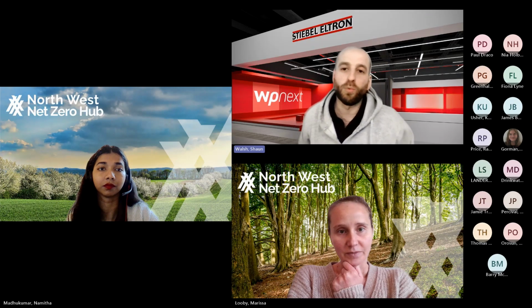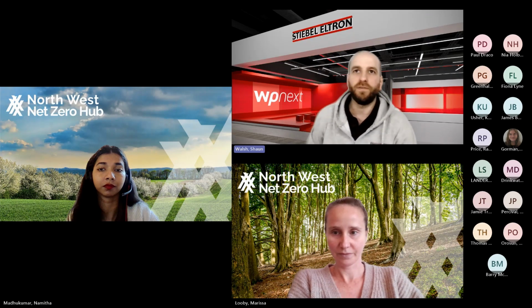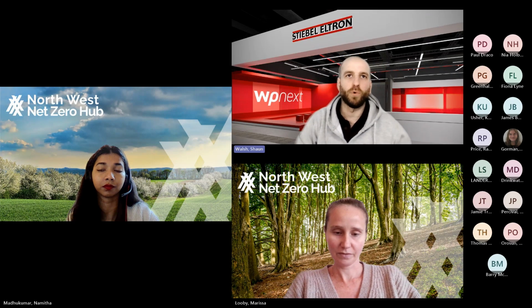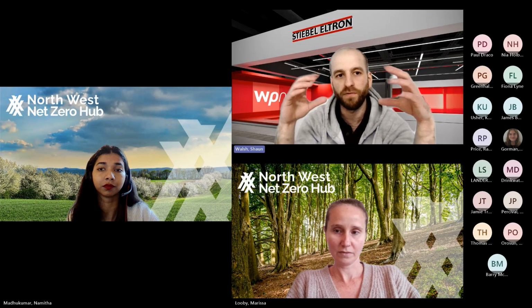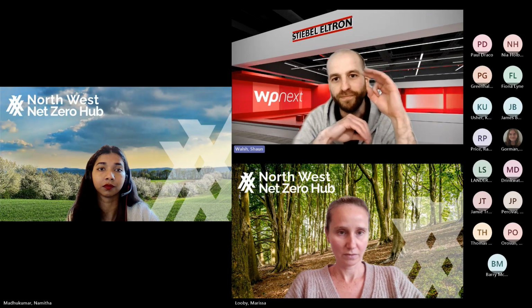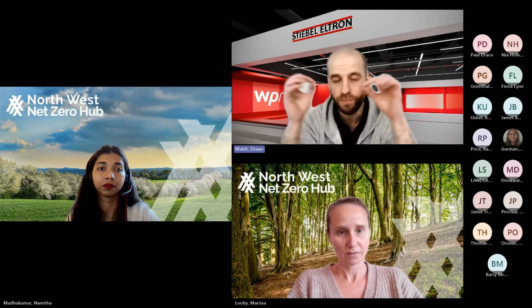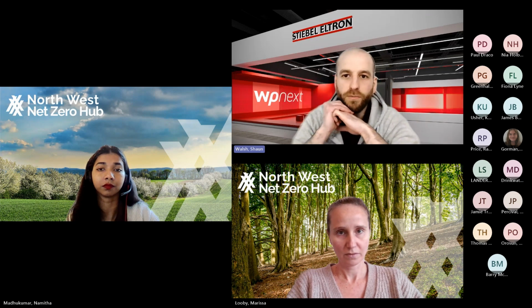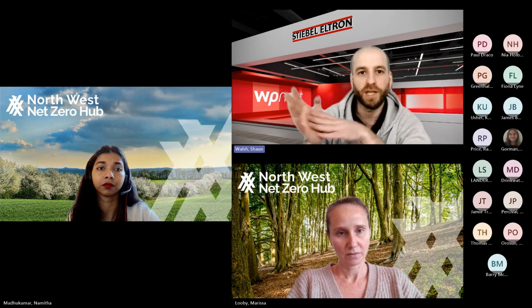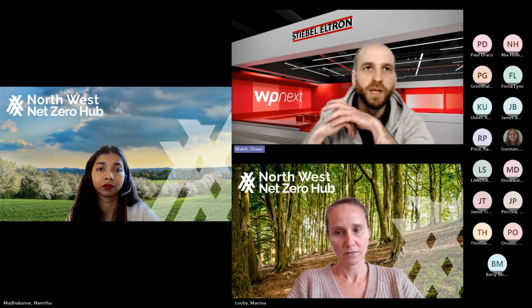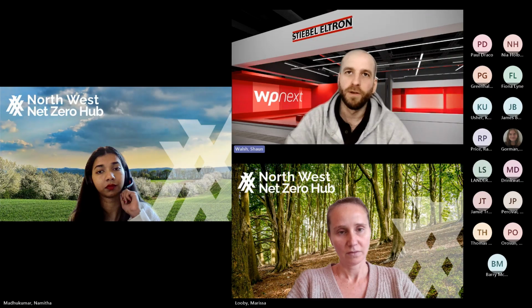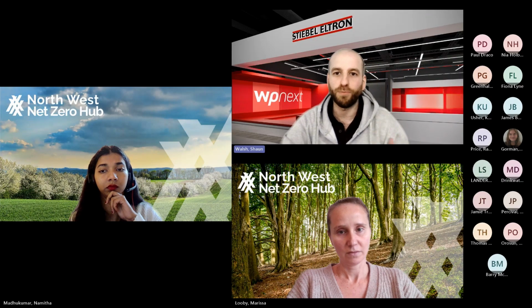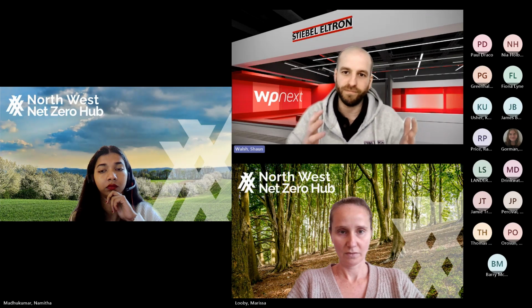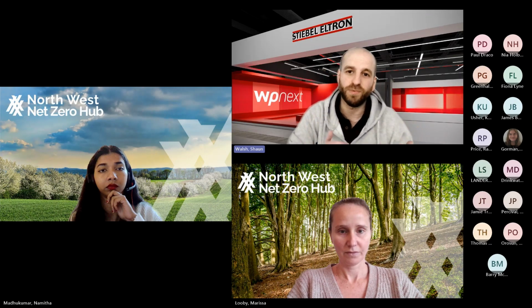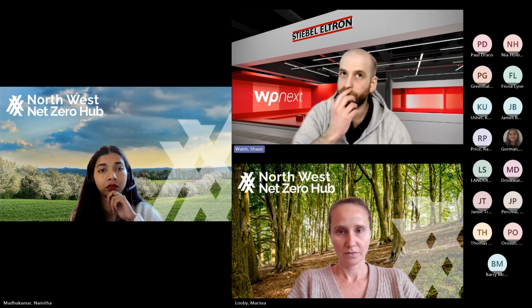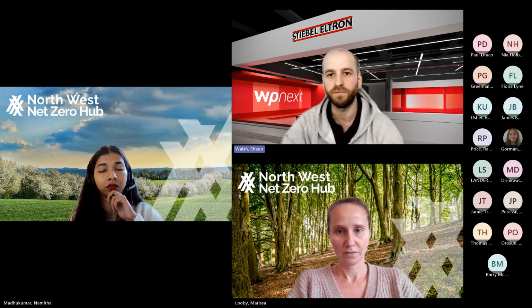No, yeah. So poor water quality can damage the heat pump itself, mainly if you get corrosion within the system. What ends up happening is the heat exchanger inside the heat pump itself is the smallest point of restriction within the whole system, because the pipework in there is so small. So if you do have any debris or build-up, if it gets past the filters you've got on the system, it will end up inside the heat exchanger of the machine. Generally, you can flush them out to try and clean them, but most of the time you can't get all of the debris out, and then it reduces the heat exchange, and your system performance drops. So it wouldn't necessarily break the machine, but it would lower the efficiency for sure.